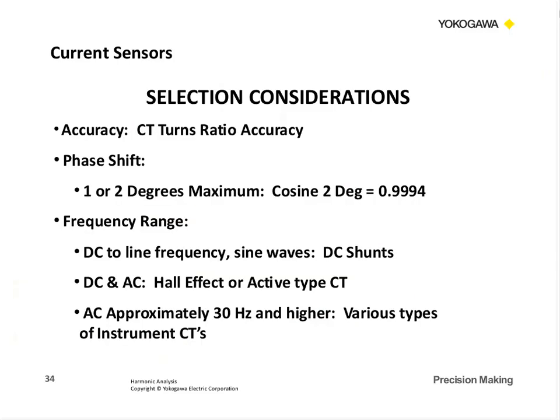So some selection considerations. Accuracy is typically defined as the CT turns ratio on the CT itself. Phase shift is very important because we're measuring power, and phase shift represents a part of the power factor. So what's acceptable to you and your application? Say if we had 1 or 2 degrees, the cosine of 2 degrees would be another multiplier, 0.9994. Sometimes that's okay, sometimes it's not. So you've got to look at that and consider your application.